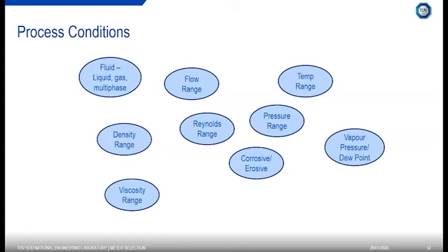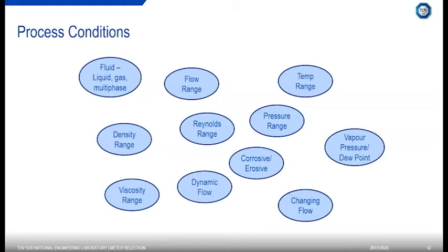Dynamic changing flow is also important. Is the flow range changing? Is it changing rapidly, throughout the day, or is it fairly stable? You need to know your minimum and maximum flow rate for turndown purposes. Some meters have a far greater flow range than others, and there will be different meter choices depending on this.